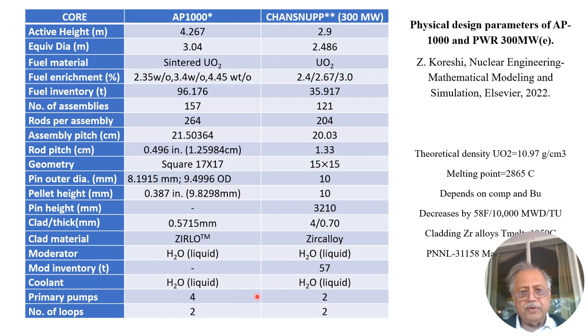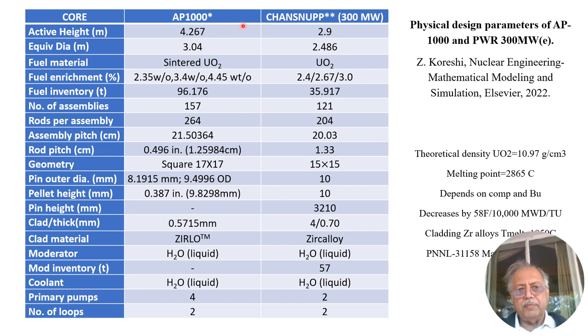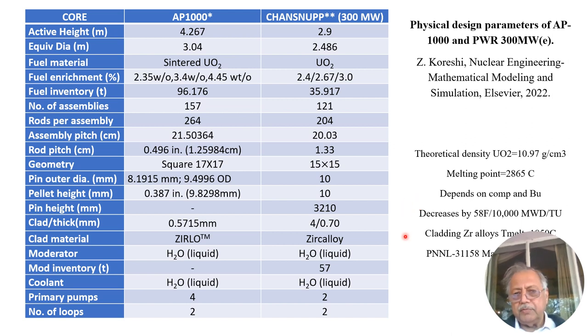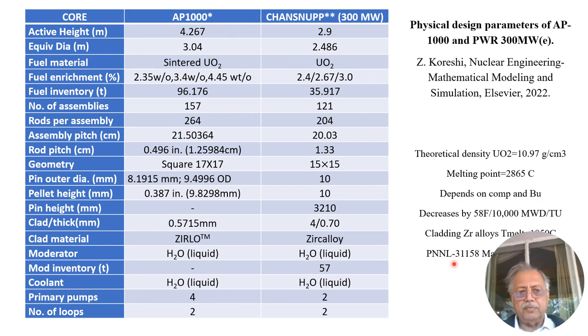The number of primary pumps depends on the coolant flow rate, which is determined by the thermal energy being removed — larger for bigger plants. The melting point of UO2 is typically 2865°C, depending on composition and burn-up; it decreases by about 58°F for every 10,000 megawatt-days per tonne. Cladding temperature data is taken from the PNNL report 31158 material libraries, which provide the relevant properties.